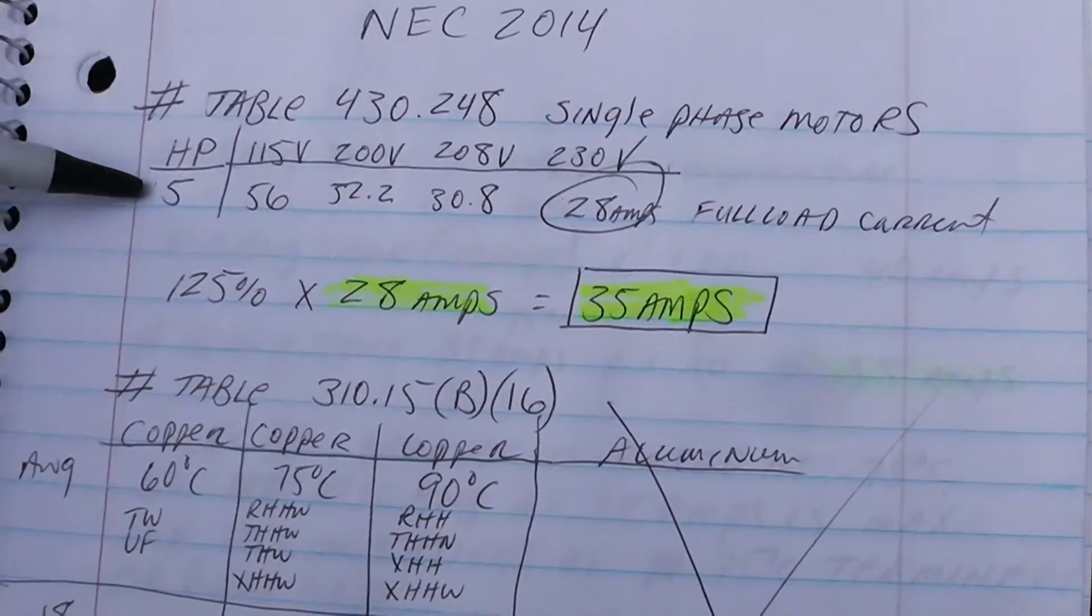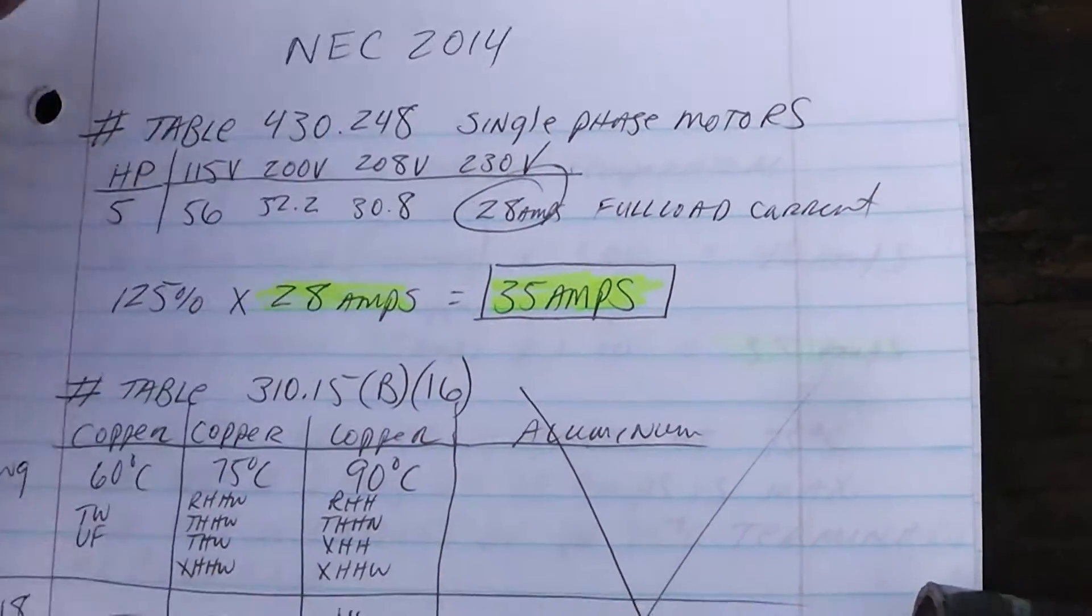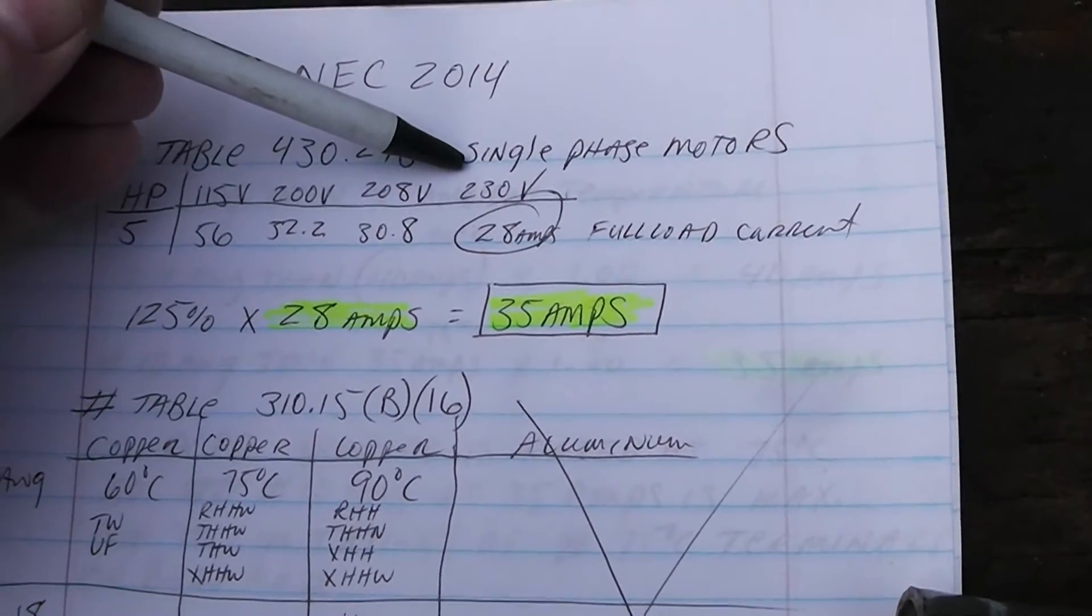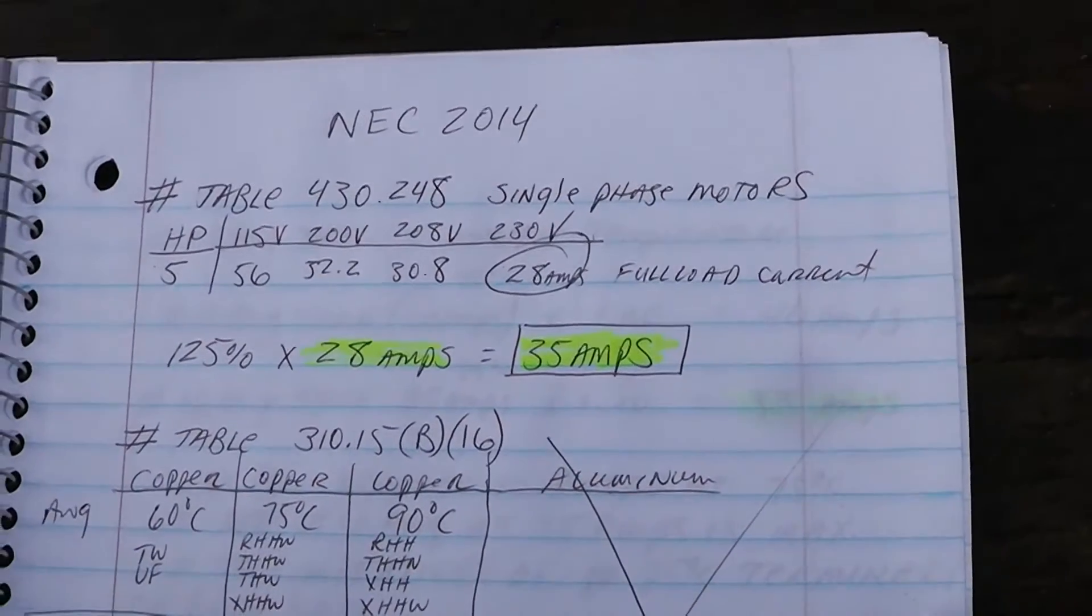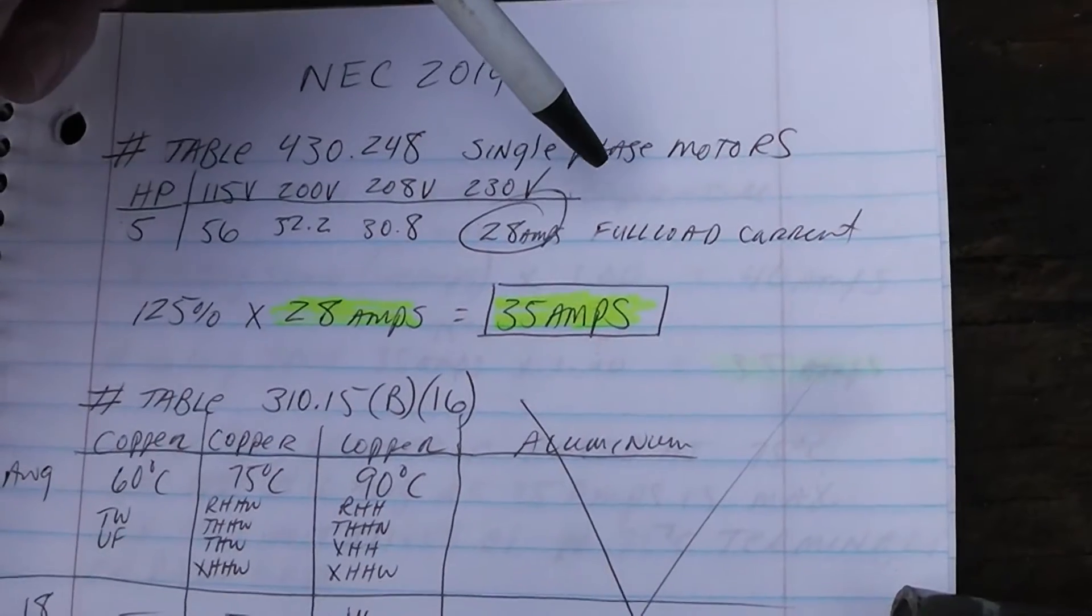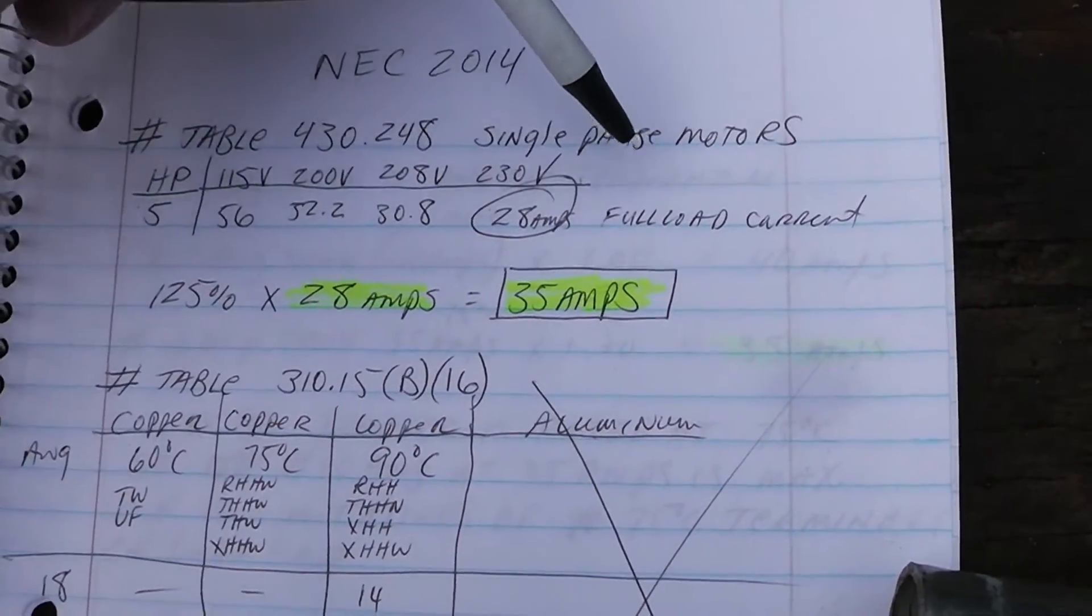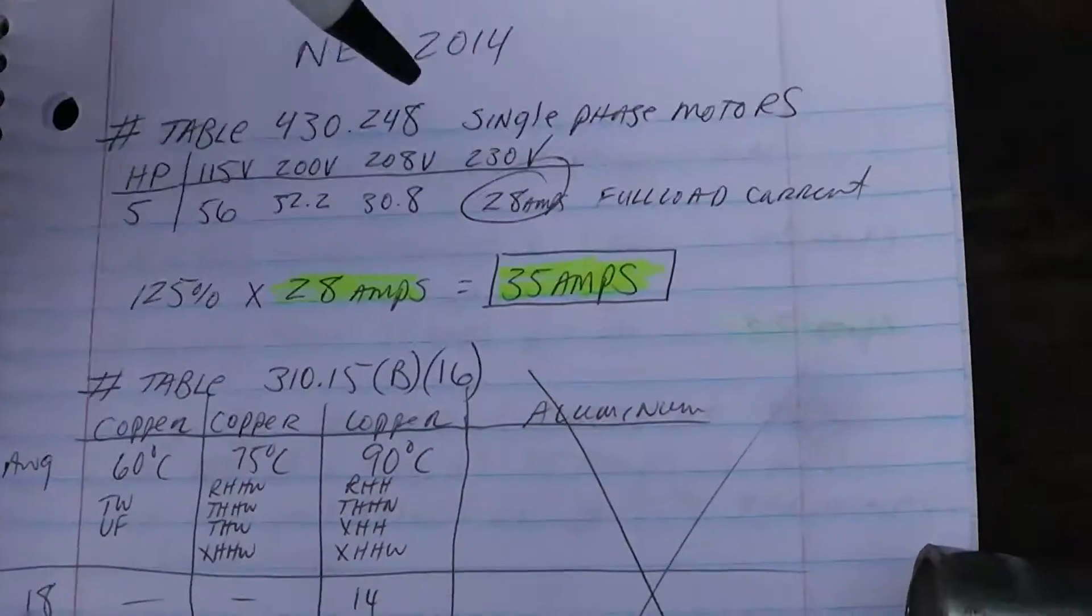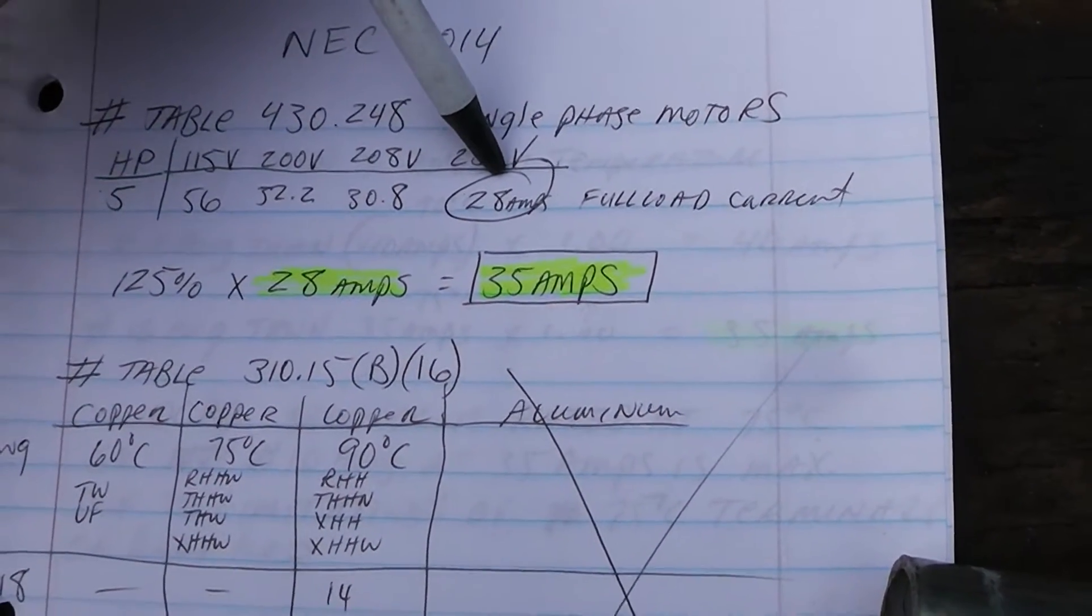We have a five horsepower motor, single phase, 230 volts, and we don't go by that nameplate rating. The nameplate said 23 but that does not apply to these motors if you're going to do it to this code. We go to this table, it says 28 amps.